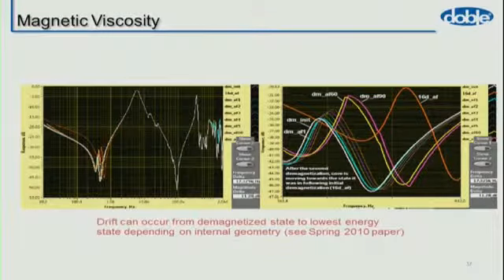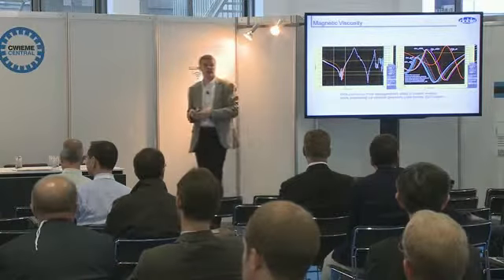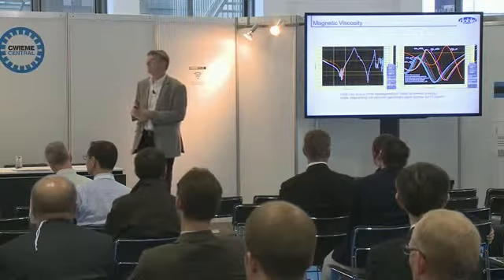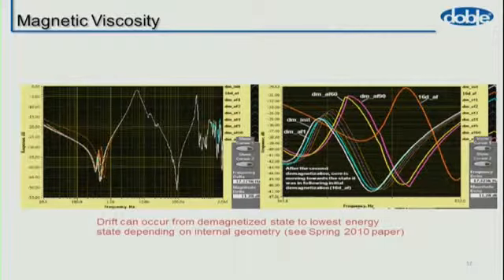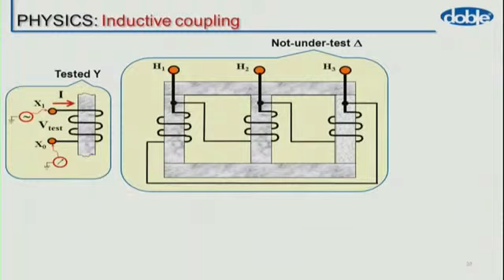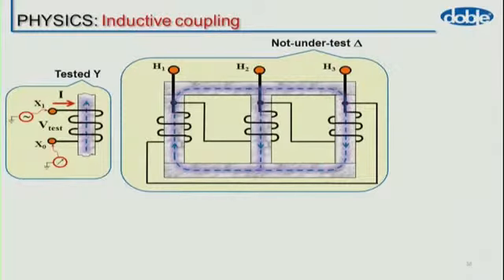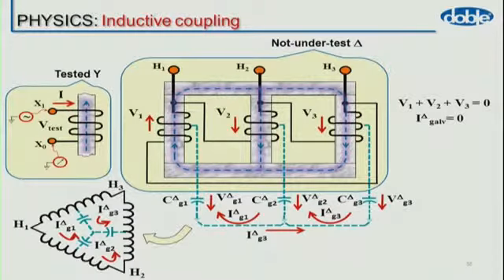Take, for example, a low frequency response. In this kind of area, that's heavily dominated by the core. It has an expected shape. That will change as the core relaxes. And the core will get to a point which is lowest total energy, lowest action. And as it relaxes, the frequency response will change. When you go and test this on site later, it's going to look different. And that's because you're measuring between 2 points, and those 2 points are electrically connected capacitively, inductively, to the whole transformer. And so you're testing everything between those 2 points.